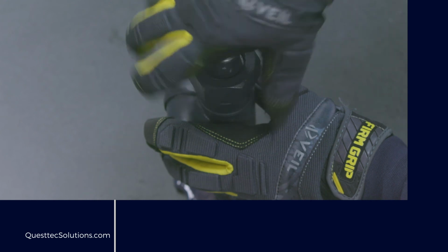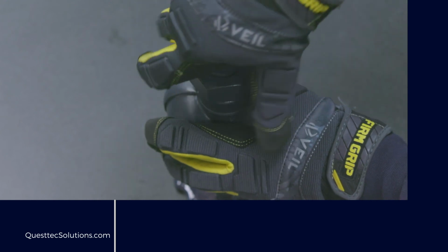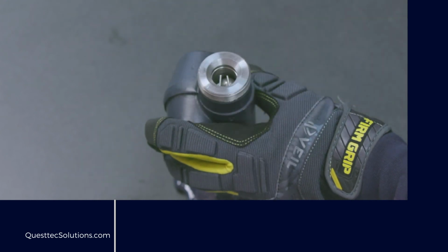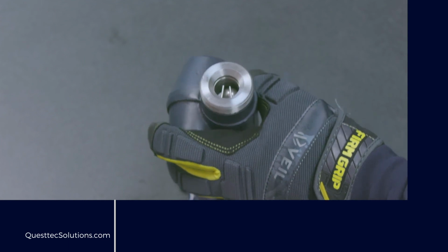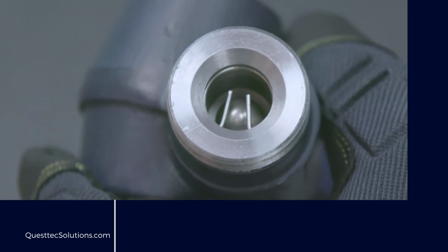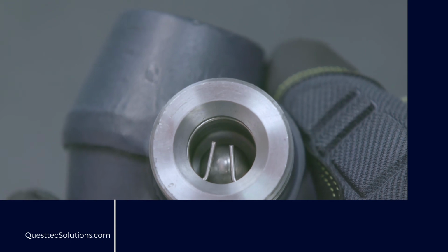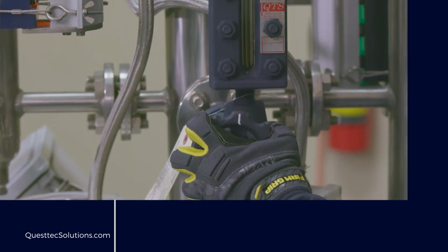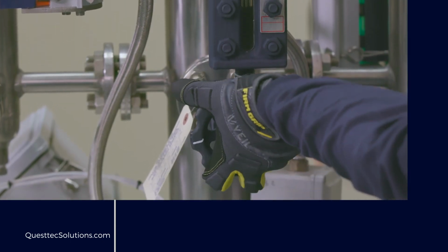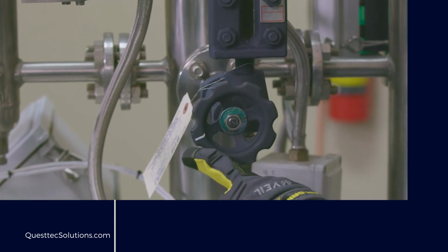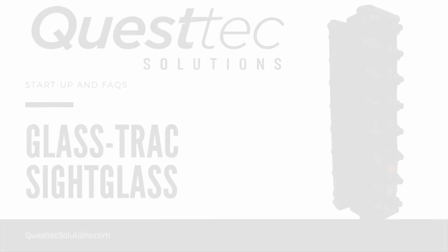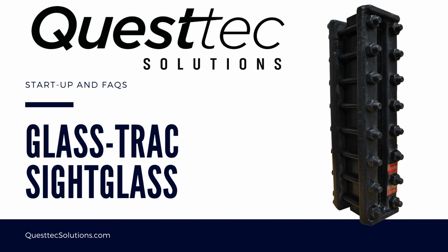Following these steps will avoid false level indications due to unintended ball check seating. If the gauge valves are immediately fully opened, the liquid level through the valve will cause the ball check to seat. The partially open 8 o'clock startup position of the gauge valve stops the ball check from contacting the ball seat.